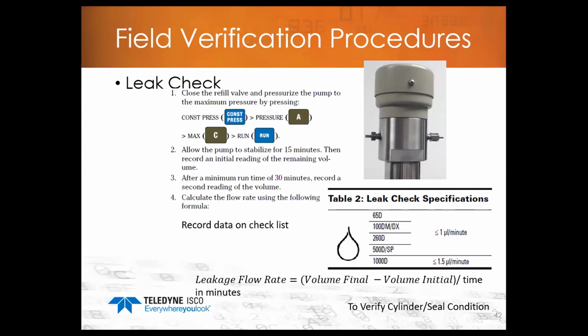So with both sides of the pump closed off, you'll have it in the constant pressure mode. You'll enter the maximum pressure for your pump, whatever pump you're running, and then press the run key. You'll let the pump run up to pressure, and once it reaches pressure, don't press the stop key. Just leave it running in the constant pressure mode, and let it stabilize for 15 to 30 minutes. Let the pump stabilize out.